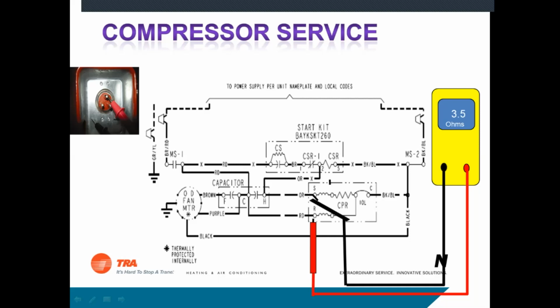Okay, so if I was to read 1.2 here and 2.3 here, and all of a sudden I read like 2.2 here, that would tell me that somewhere I have a shorted winding inside that compressor. So it should all add up. It should add up to the value of these two different windings. And that's all we're doing, is we're taking a reading through the compressor through both sets of windings instead of going back to ground.